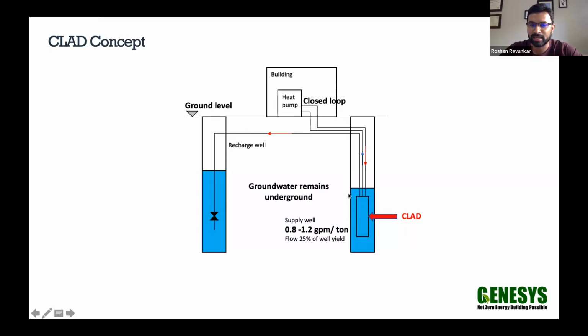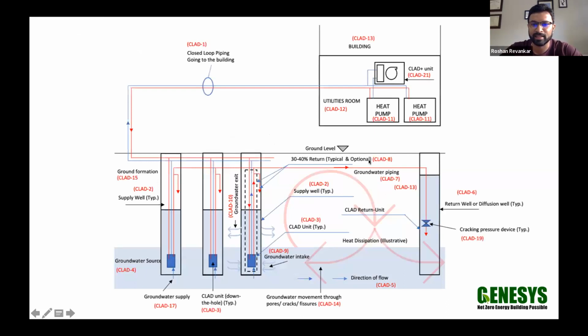The neat thing about the way CLAD is designed is all of the open loop piping and all of the water essentially stays below ground level. We've noticed that authorities like that, and that's one of the features of CLAD, that all of the groundwater never leaves the ground or never sees the light of day. Now, in reality, this is a little more complicated diagram, but essentially the same concept. You could have a building with multiple heat pumps. Supply and return coming from the building, going into a header system, into closed loop or CLAD wells. You can think of these as very similar to how a typical closed loop bore field would be designed. But in this case, you need a lot fewer CLAD wells compared to a typical closed loop system. In reality, you need only 2 to 3 supply wells for every discharge well. We don't need a one-on-one correlation on the supply and discharge.